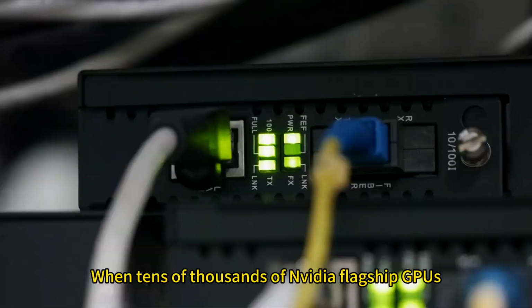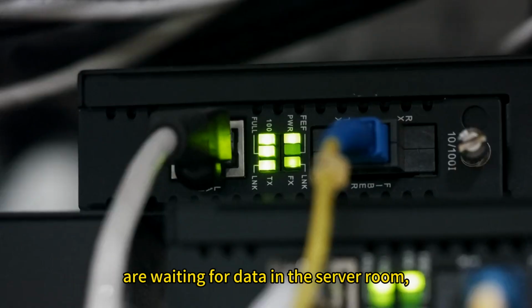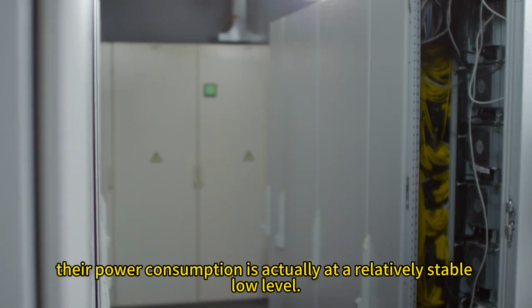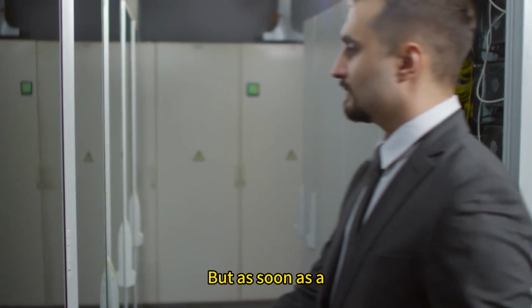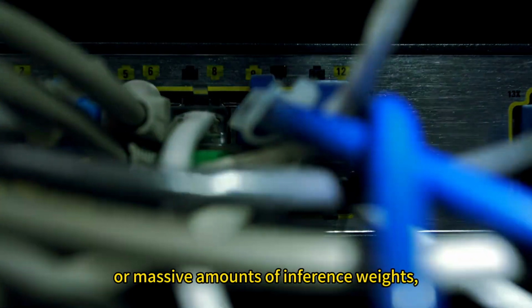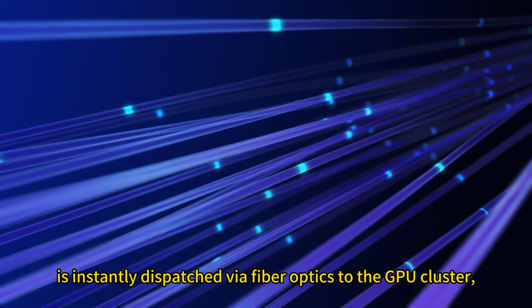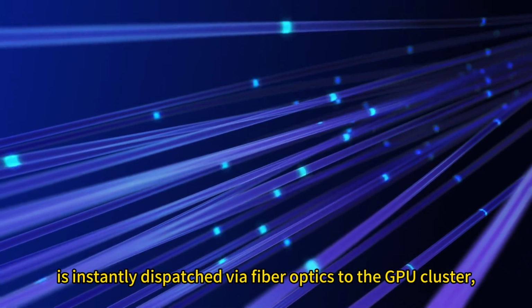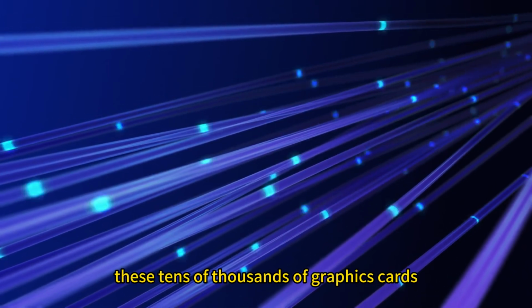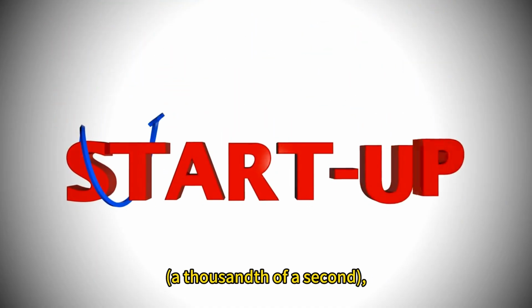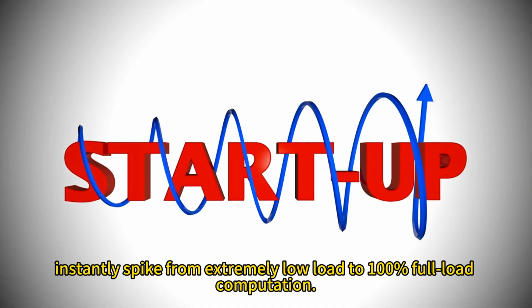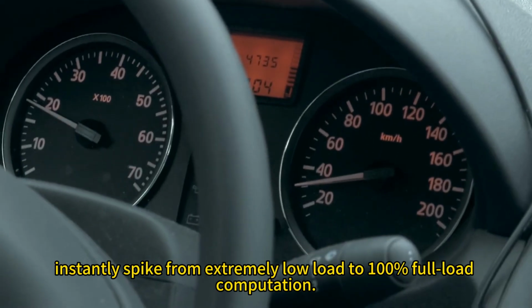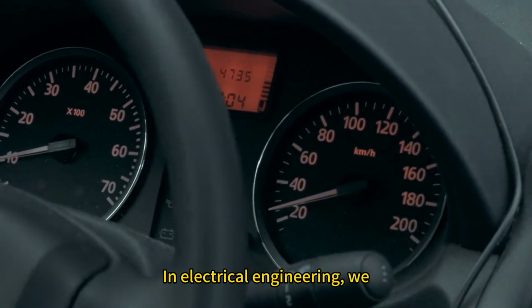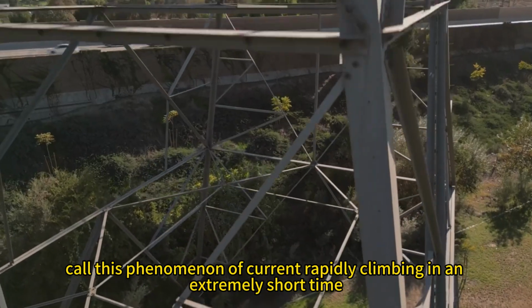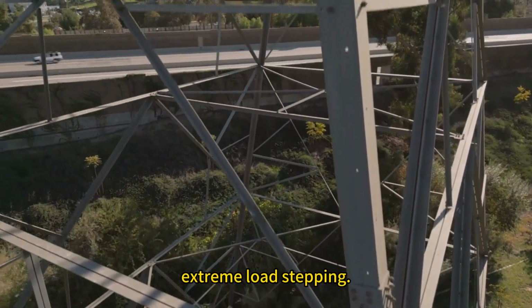When tens of thousands of NVIDIA flagship GPUs are waiting for data in the server room, their power consumption is actually at a relatively stable low level. But as soon as a large language model training task with hundreds of billions of parameters, or massive amounts of inference weights, is instantly dispatched via fiber optics to the GPU cluster, these tens of thousands of graphics cards will, in just a few milliseconds, a thousandth of a second, instantly spike from extremely low load to 100% full load computation. In electrical engineering, we call this phenomenon of current rapidly climbing in an extremely short time extreme load stepping.